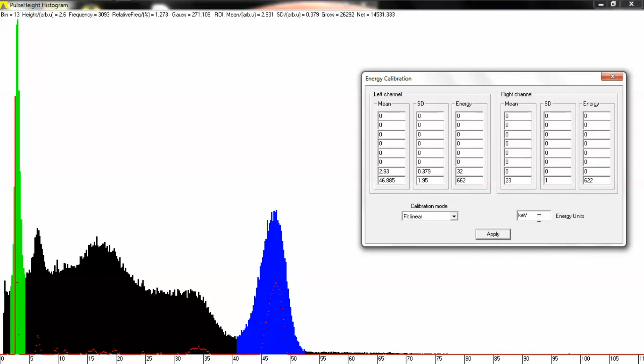And the energy unit is in kiloelectron volts. That's thousands of electron volts. Don't worry about right channel unless your unit uses right channel. My unit's only using left channel, so we're good. So click OK. And we're applied, if you like. So let's go over here and say use energy calibration. And now we're fully calibrated down here with energies.